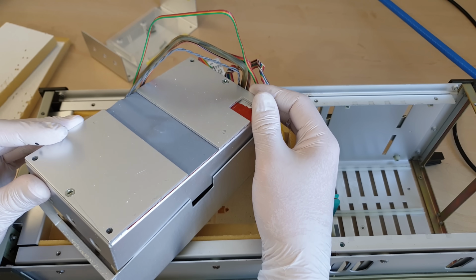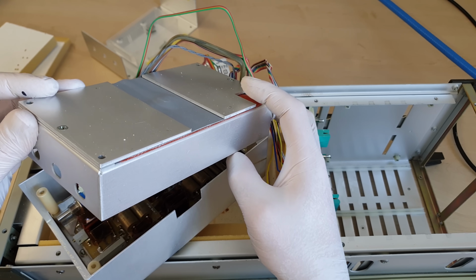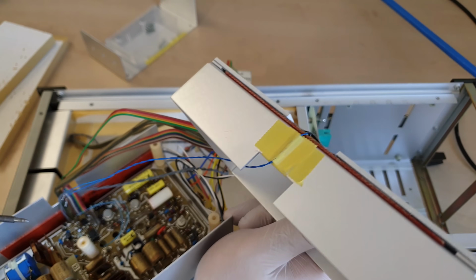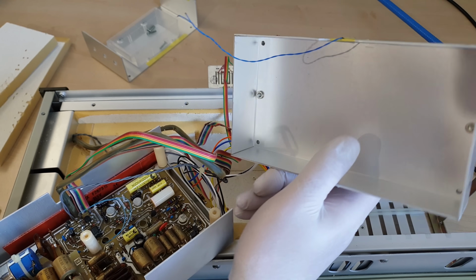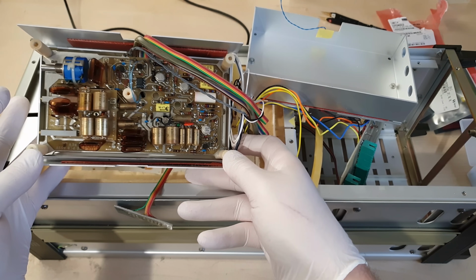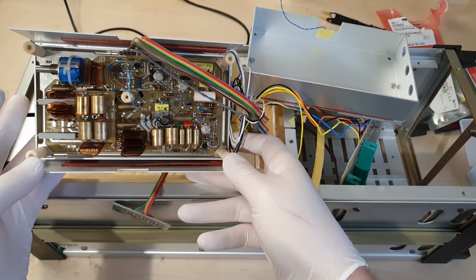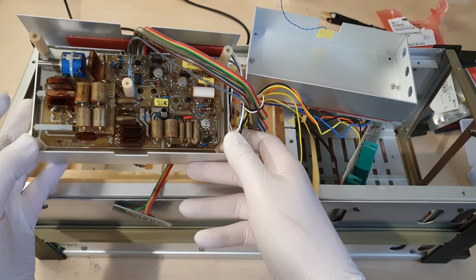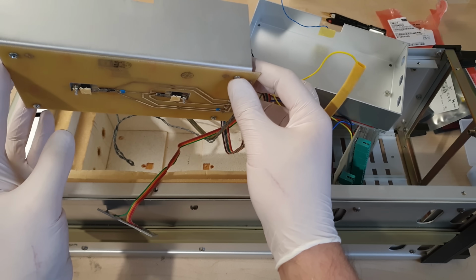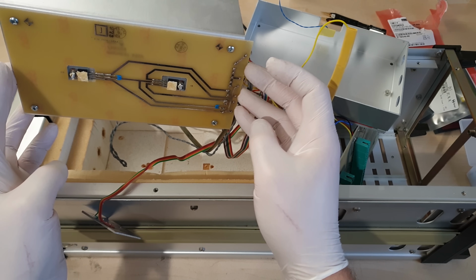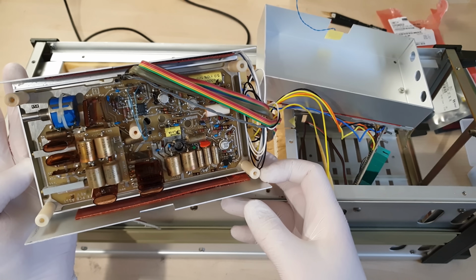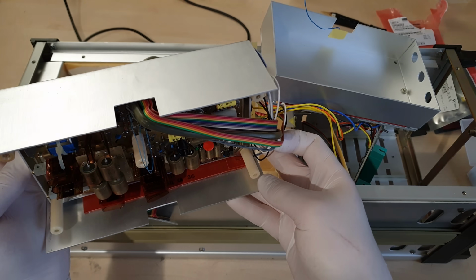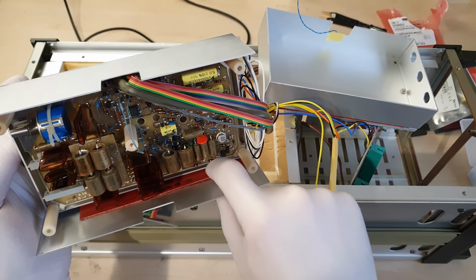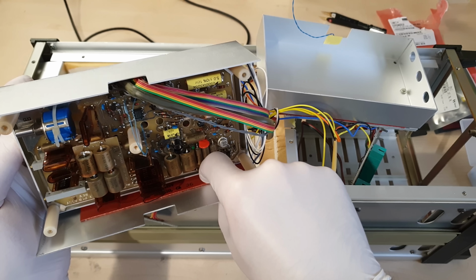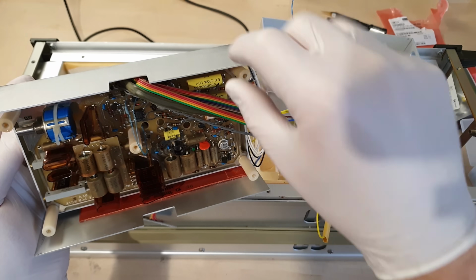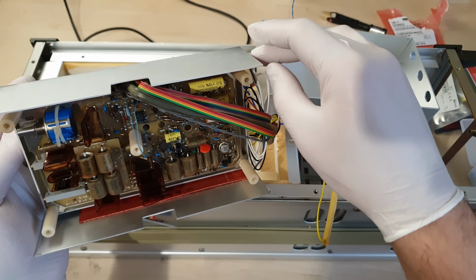There are 3 major thermal effects at play that have to be managed for this assembly to achieve best performance. First, our old friend the thermocouple effect that can generate microvolts and therefore ppms when junctions of dissimilar metals are at different temperatures. A tinned copper circuit board, gold-plated Kovar component leads, nichrome resistance wires, and platinum resistance thermometers. None of this can be engineered away easily. So, care is taken to heat everything evenly, with these orange silicone heat pads on all walls. Who would have thought that there were applications for these other than 3D printers?